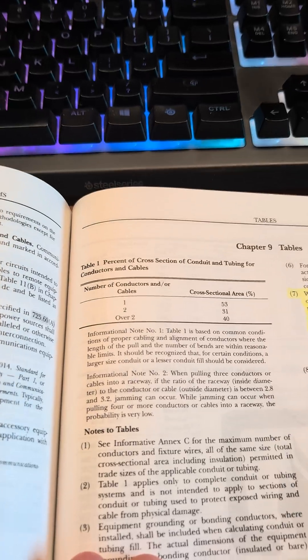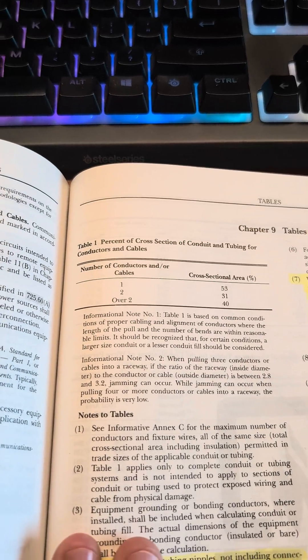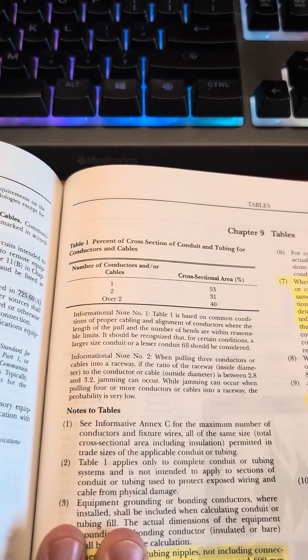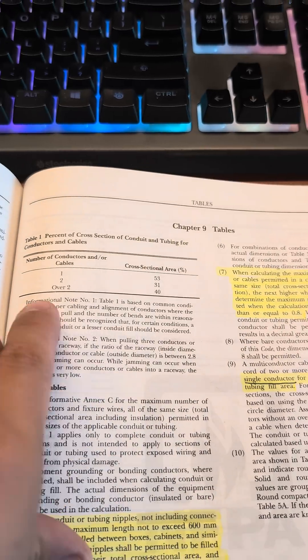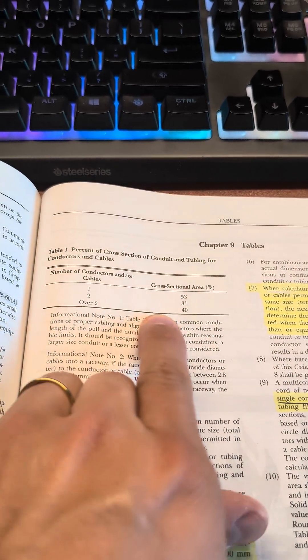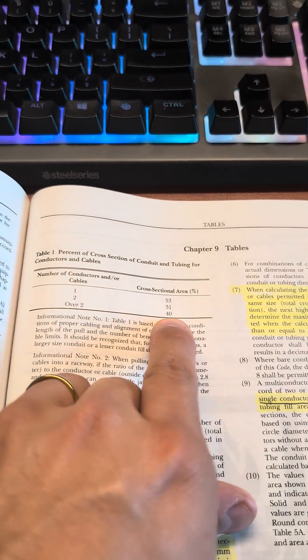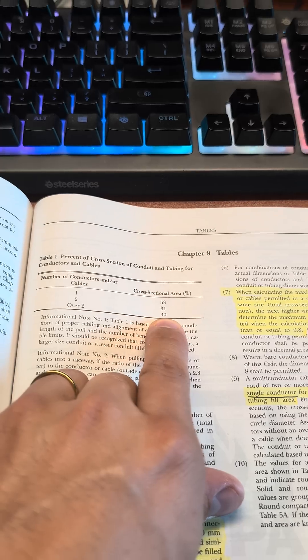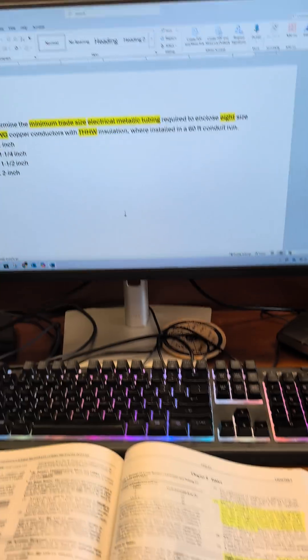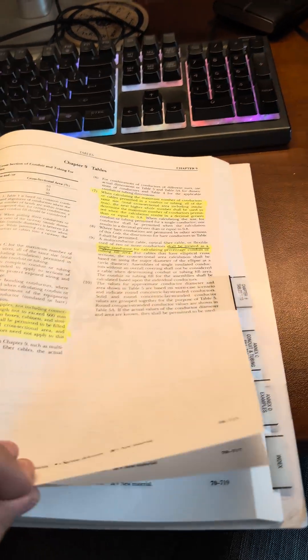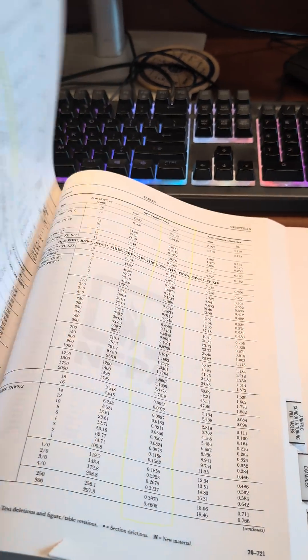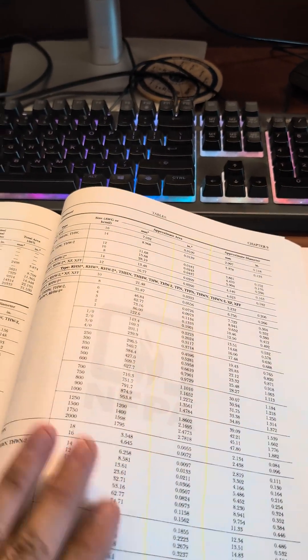First, we've got to look at Table 1 — Percentage of Cross-Section Fill of Conduit and Tubing for Conductors and Cables. Since we have 8 wires, that's over 2, which means we're only able to use 40% fill of the conduit. It seems like a little bit, but it's actually not too bad.